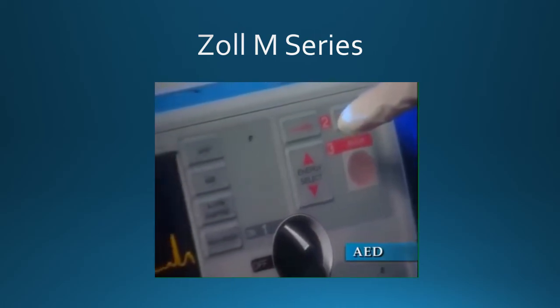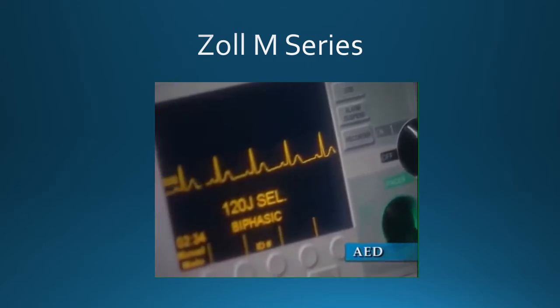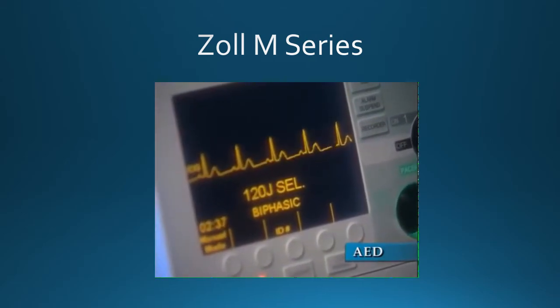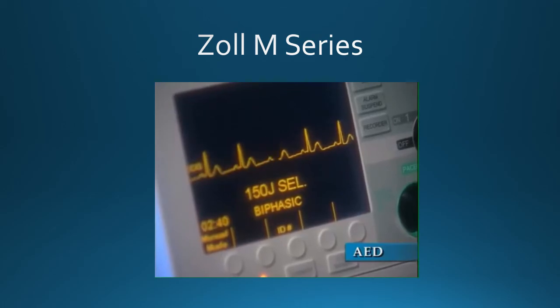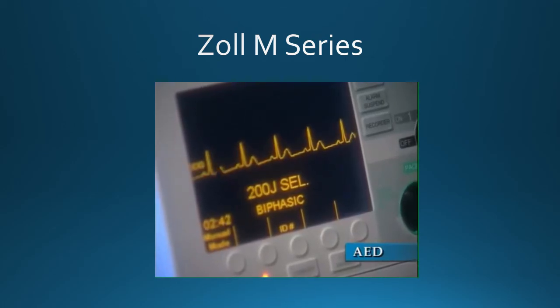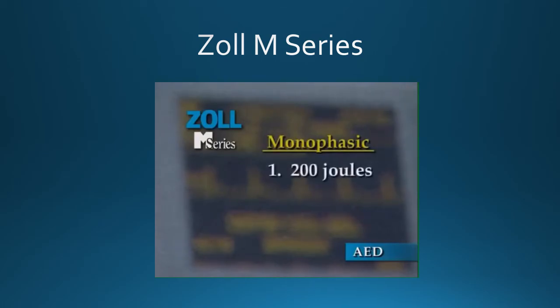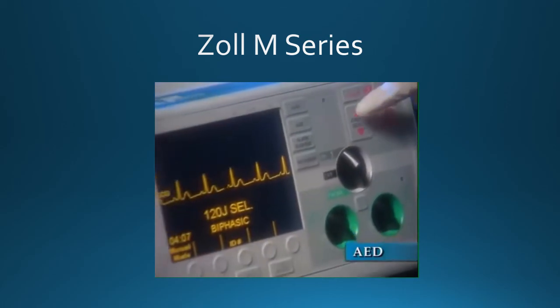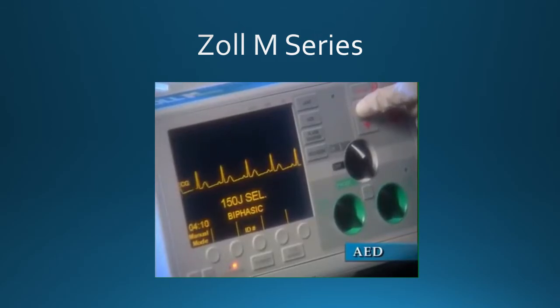Biphasic M-series defibrillator default settings are shock number 1 at 120 joules, shock 2 at 150 joules, and shock 3 and up set at 200 joules. If your M-series utilizes a monophasic waveform, default settings are 200, 300, and 360 joules. If medical protocols allow, the operator may select any of the pre-configured energy levels using the Energy Select up or down arrow buttons. The new energy level will display on the monitor.